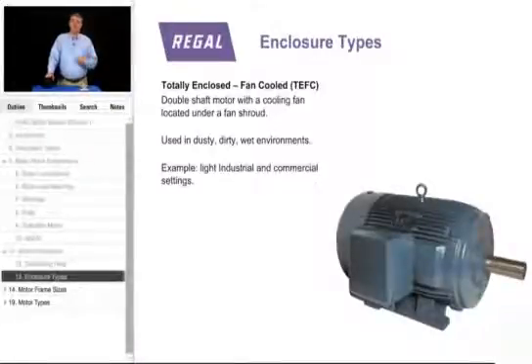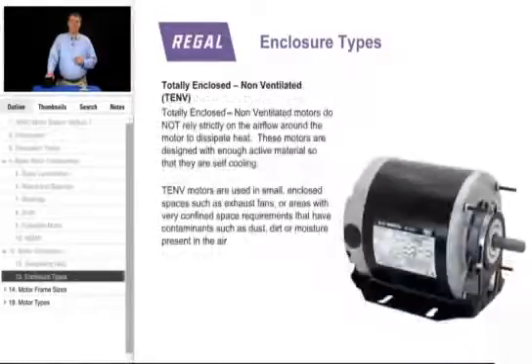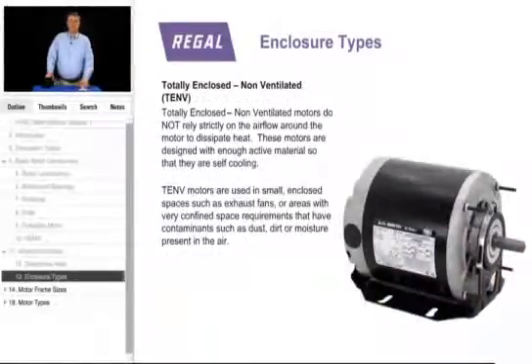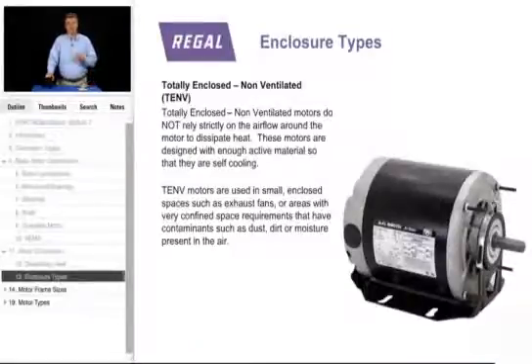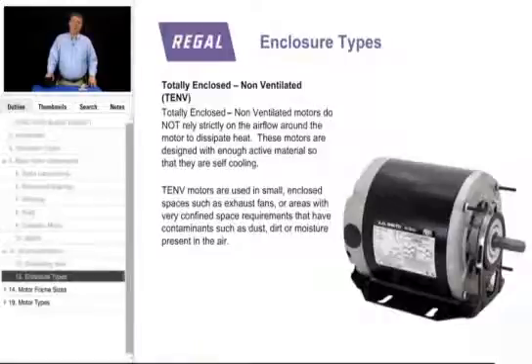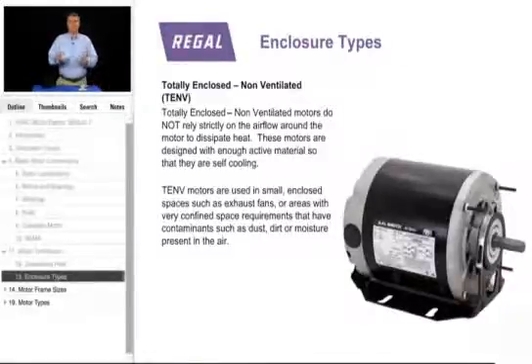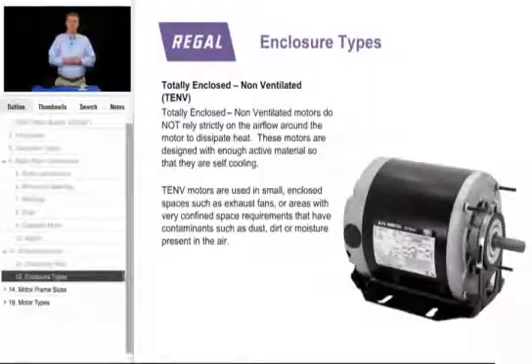Totally enclosed non-ventilated motors, or TENV, again have an entirely enclosed case construction. However, in this case there is no air flow directly over the motor. They may be located in small enclosed spaces where there is not a lot of air flow, so we have to build this motor longer to provide more shell size to help dissipate heat.